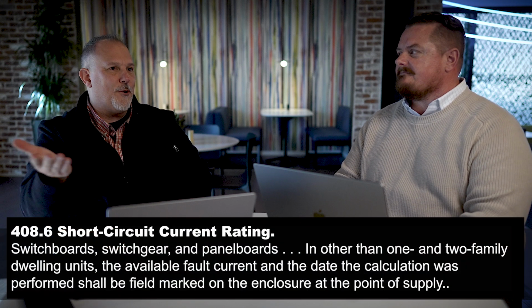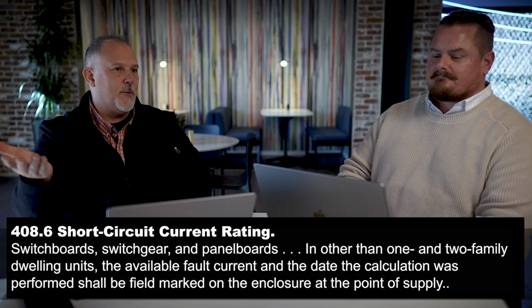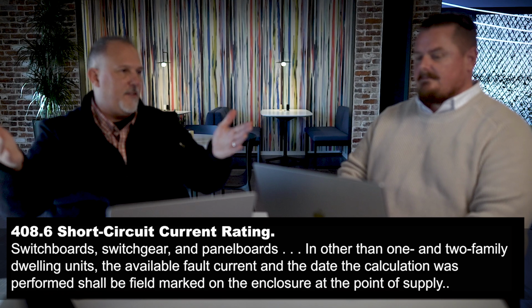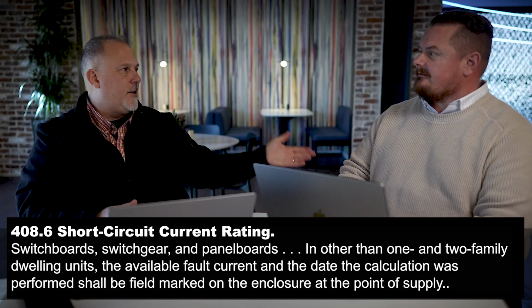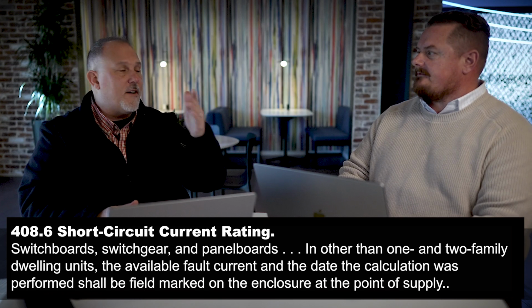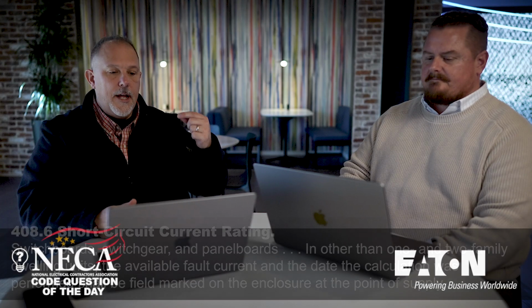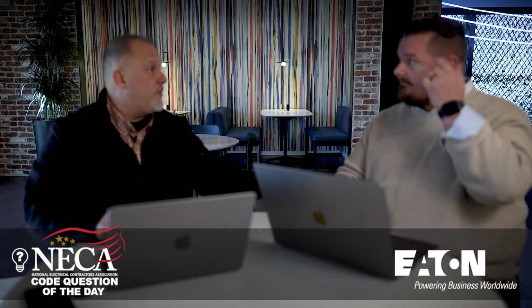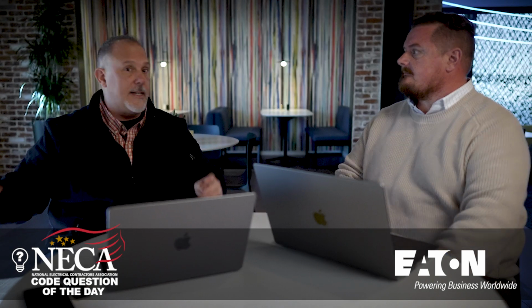You got Article 408 that tells you every panel board, switchboard, and switchgear has to be labeled with an available fault current. 2026 code is going down the road of saying you have to have arc flash labels on your equipment. From a short circuit current rating, you've got 110.10. I could make the argument you don't need any other reference to short circuit current ratings anywhere in the code because it's in 110.